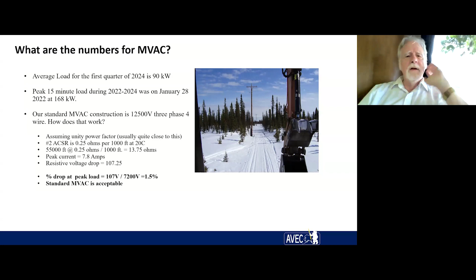if this was installed as an AC line using 12.5 kV installation, which is normally our standard, it'd be a 1.5% drop at peak load. This is quite acceptable. There's nothing wrong with putting an MVAC line in this installation. So why DC? Next slide, please.